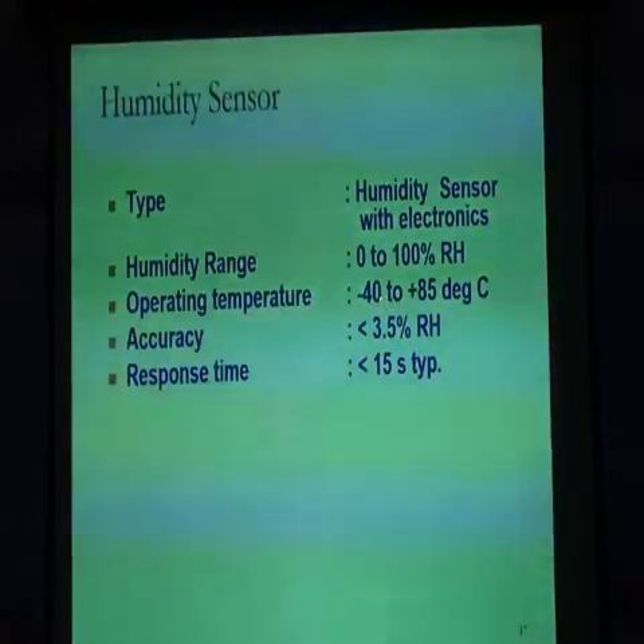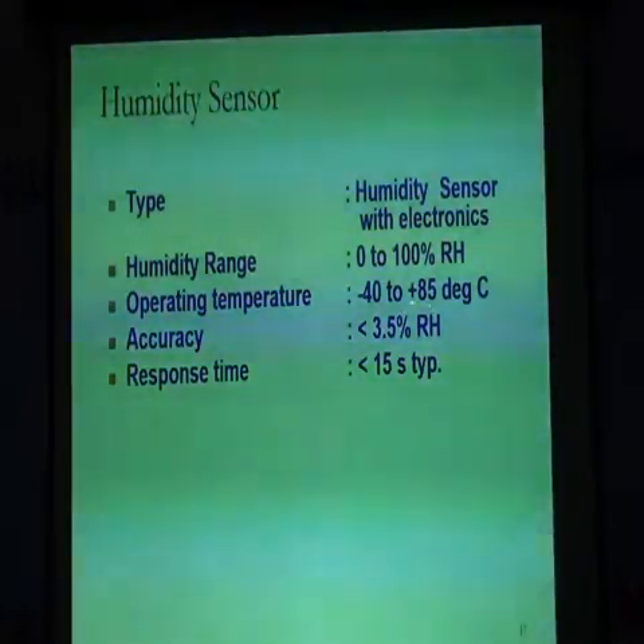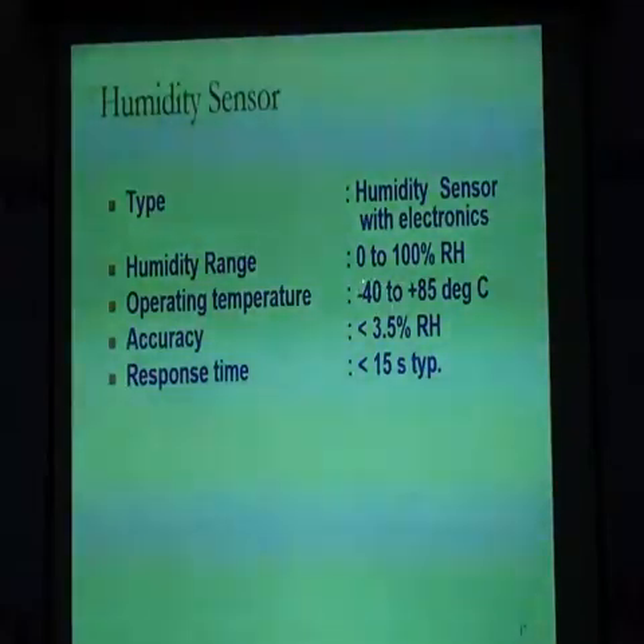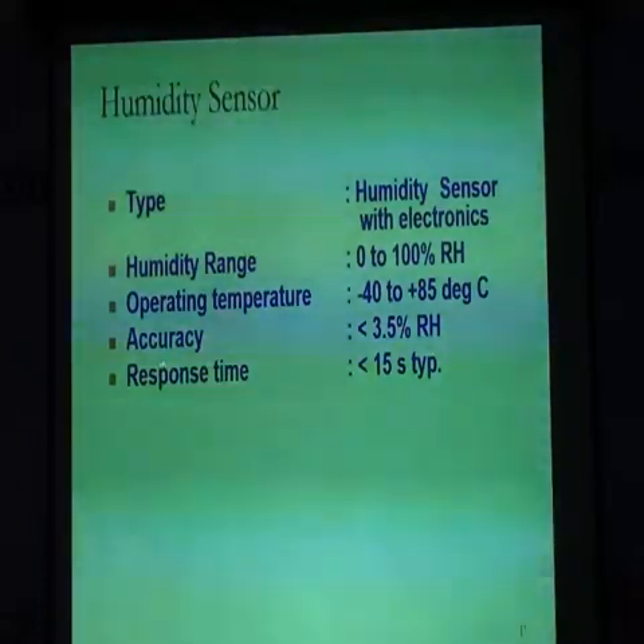So I would like to tell you that after -40 degrees centigrade, there is practically no humidity. It will give error results. I can show you the results. Black results are coming. So there is no humidity below -40 degrees centigrade. Then the accuracy is less than 3.5%, and the response time is 15 seconds typically.